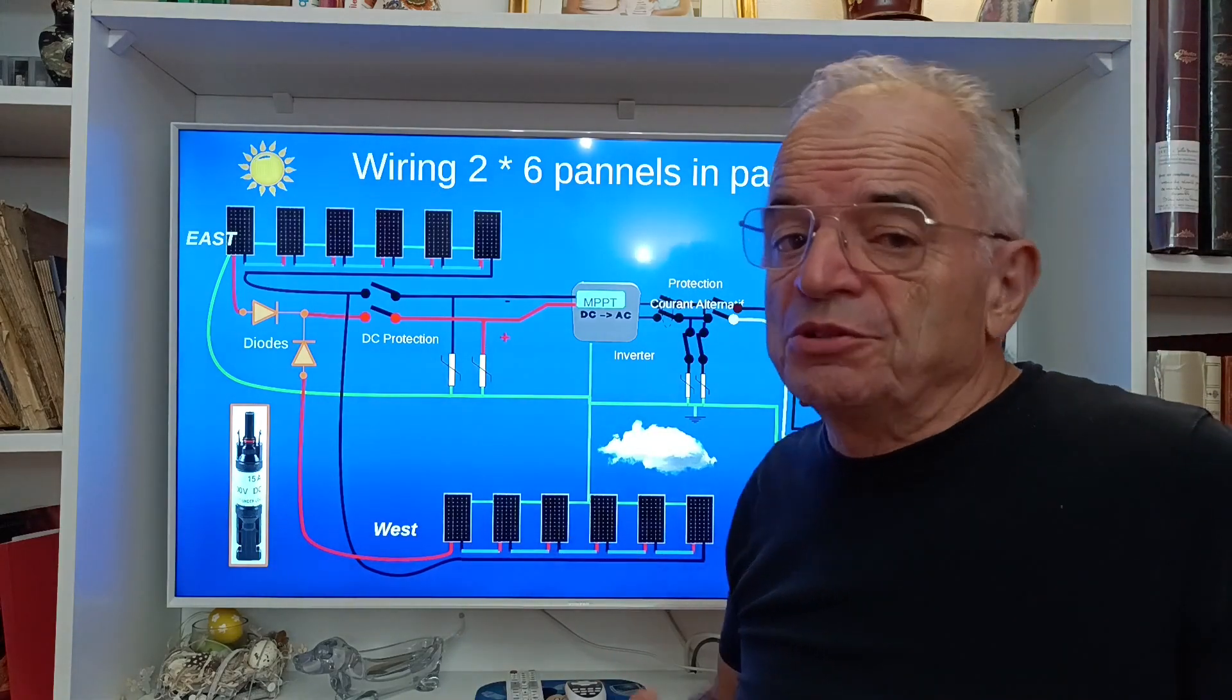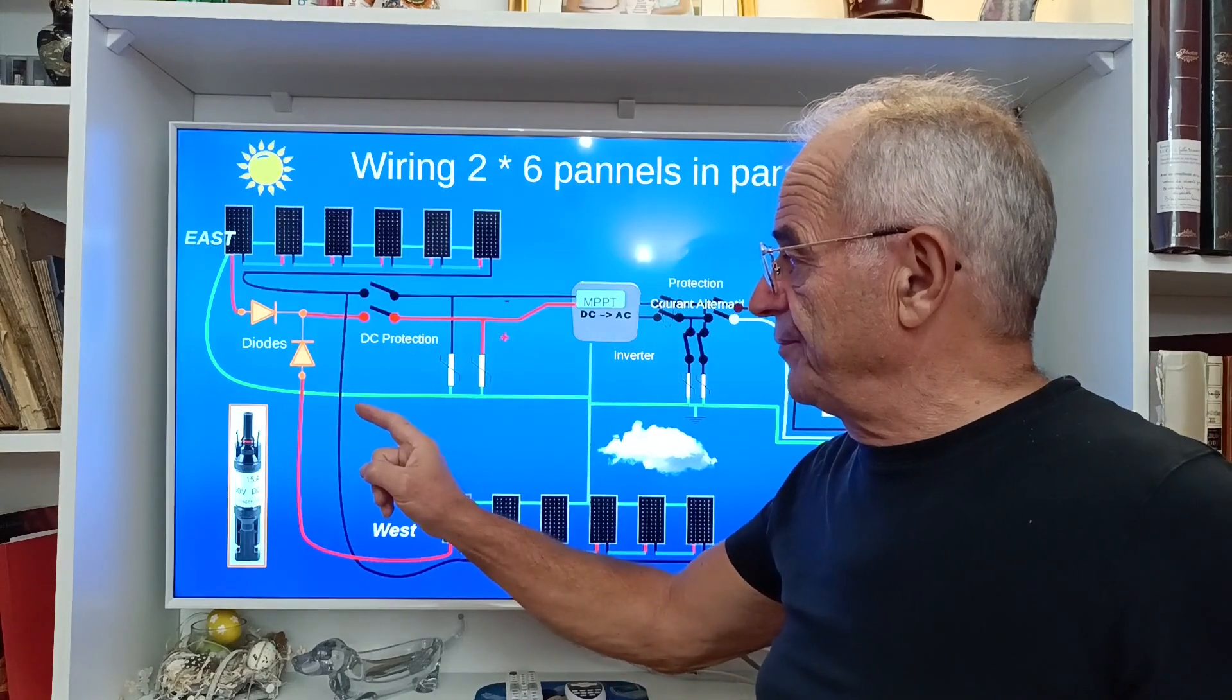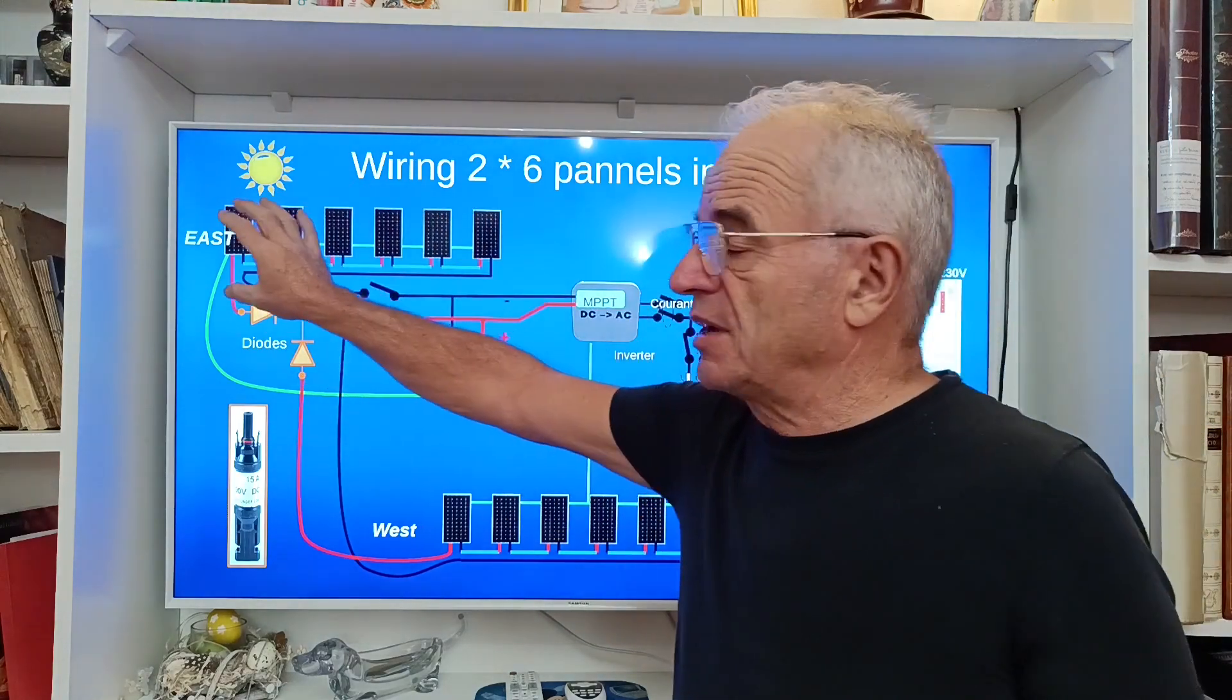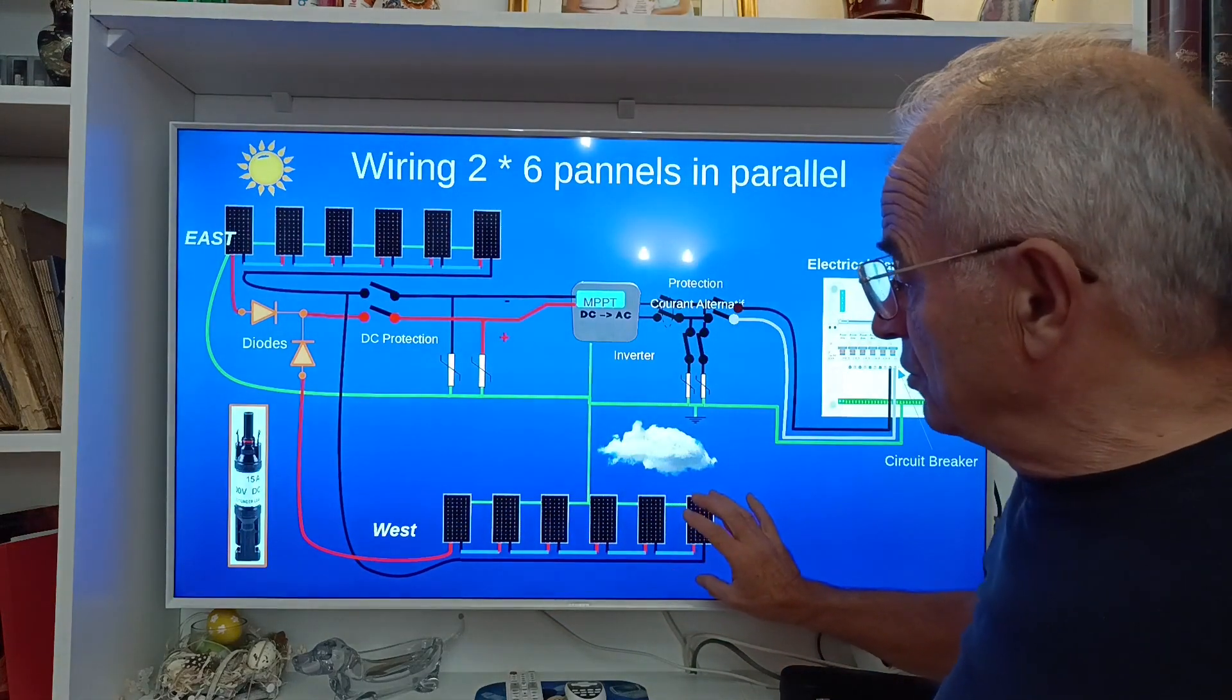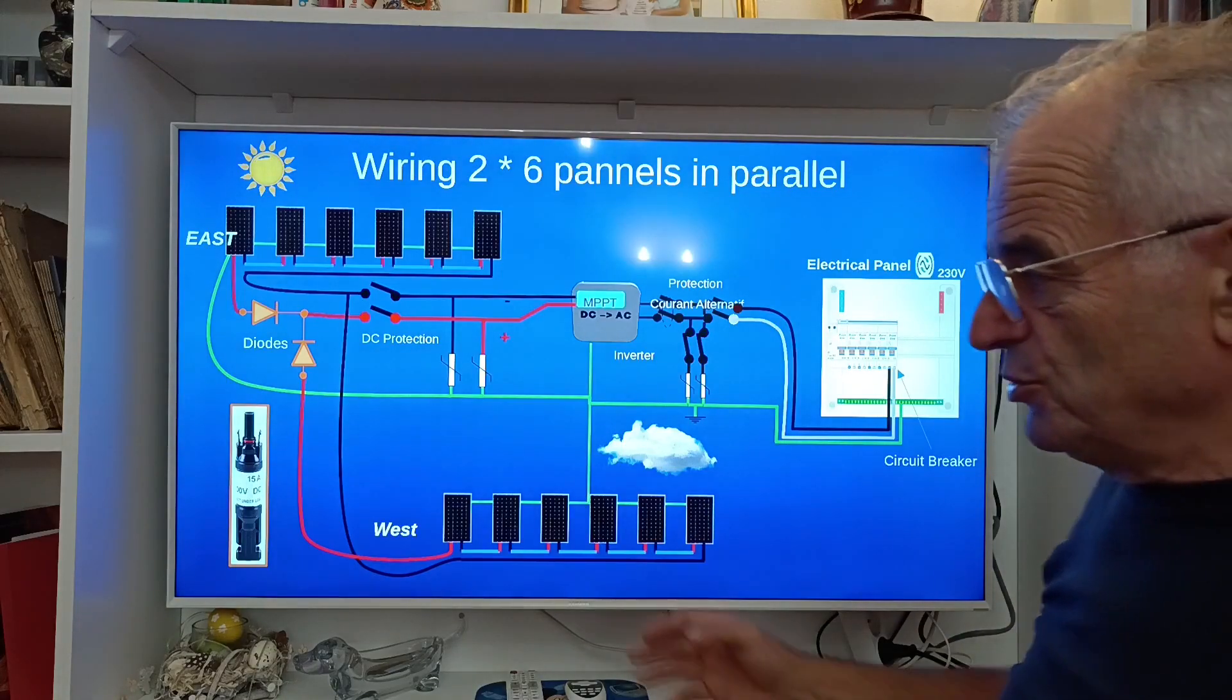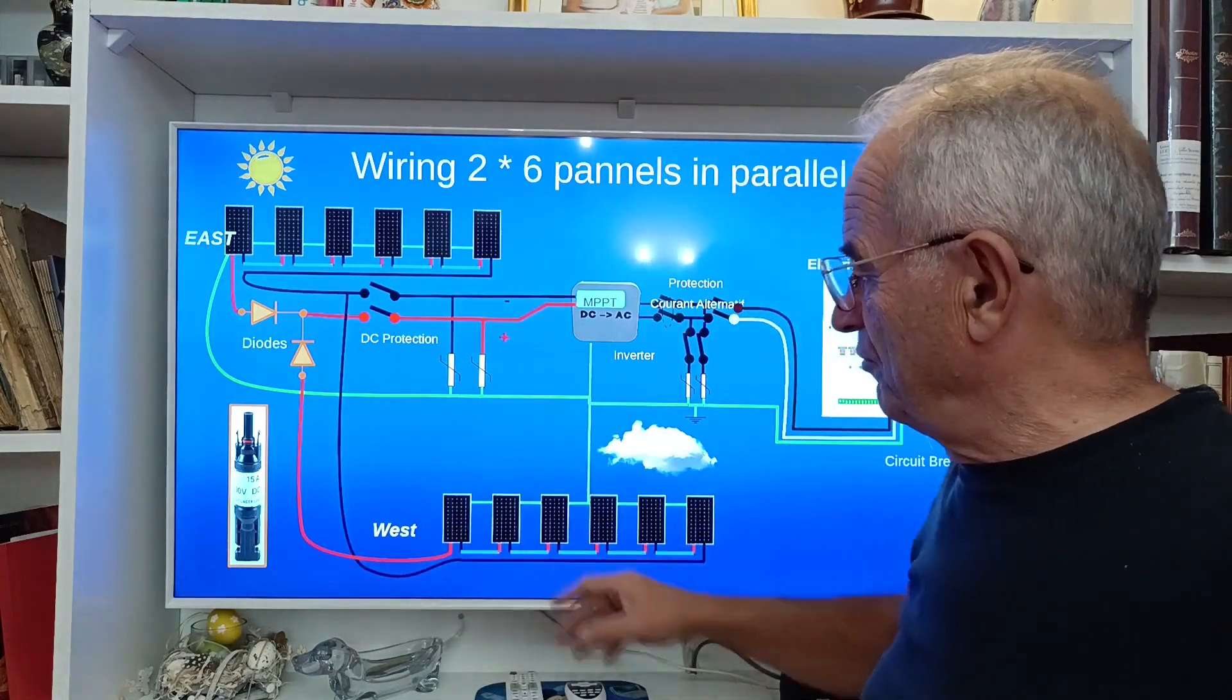The only drawback with such configuration is that if the voltage of this one is lower than this one, the tracker will track the characteristics of this group, and you are not in an optimal position to extract the maximum of energy of this group. But this suppresses the risk of fire.